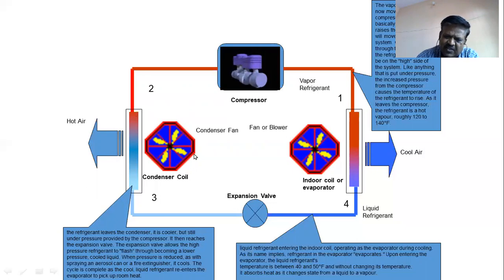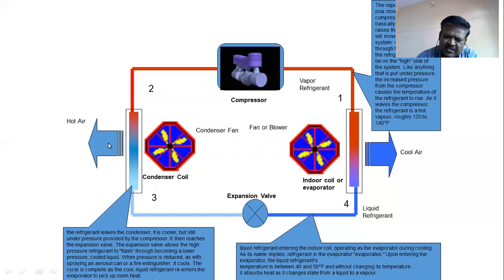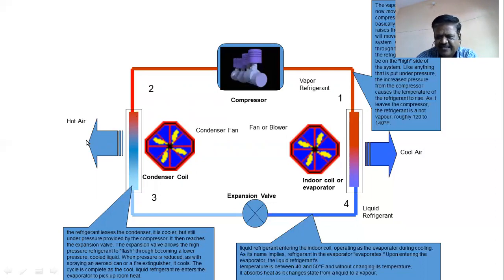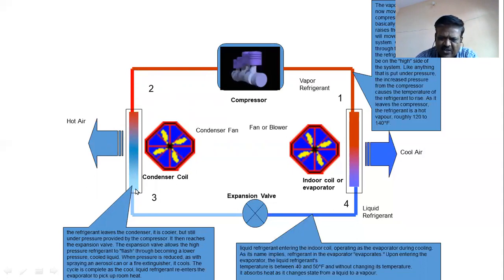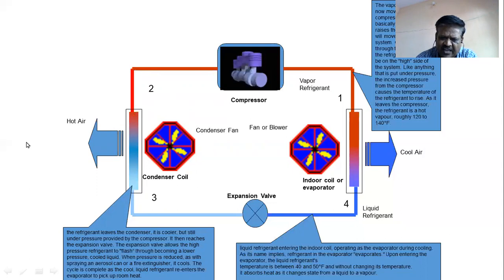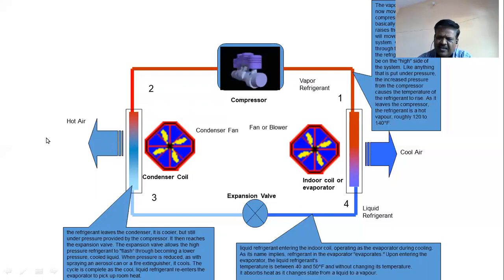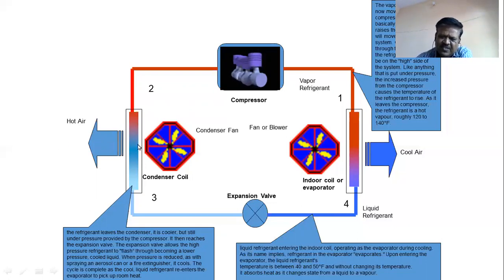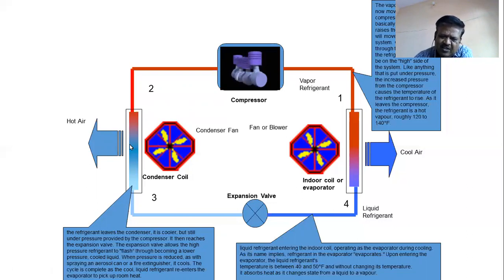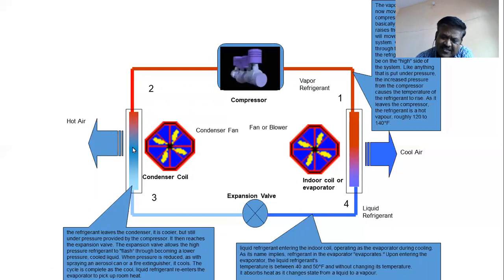The purpose of compressing is not to produce heat — it is a natural phenomenon that when you compress, heat is produced. So the hot, high-pressure gas goes to the condenser. In the condenser, with the help of a cooling fan, they cool down the gas — removing the heat from it. When this high-pressure hot gas circulates through the condenser, the fan exchanges the heat. When the heat is removed from the gas, it goes back to liquid state — it becomes a liquefied gas.